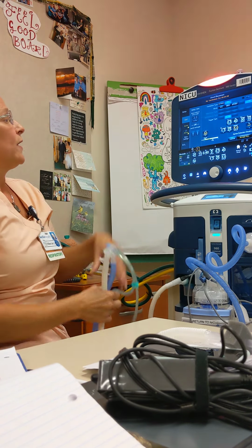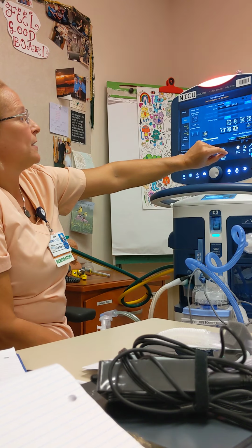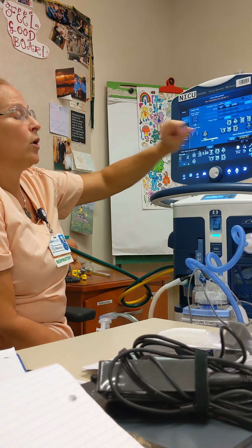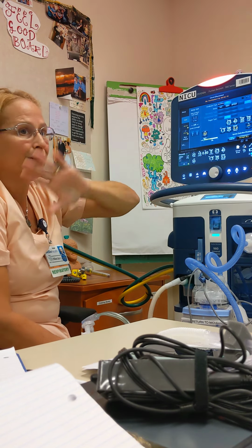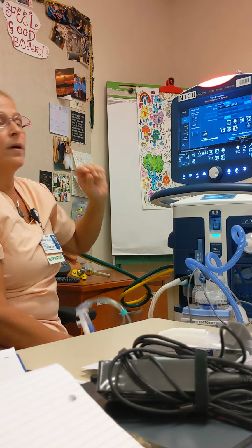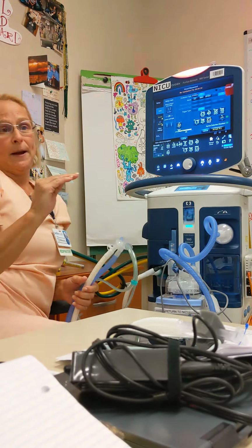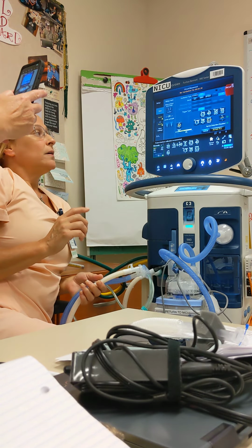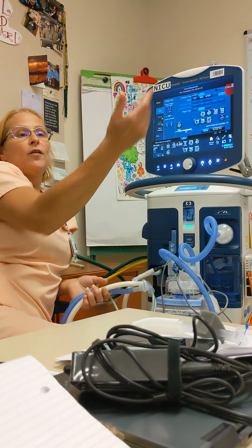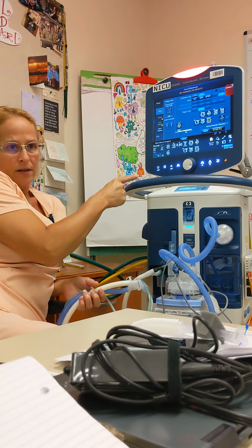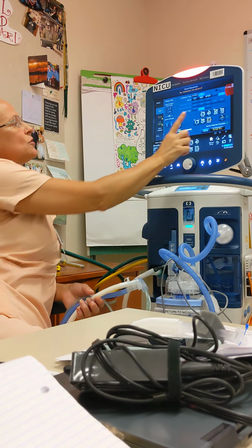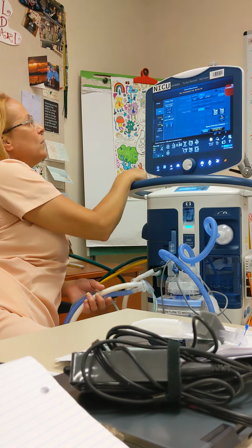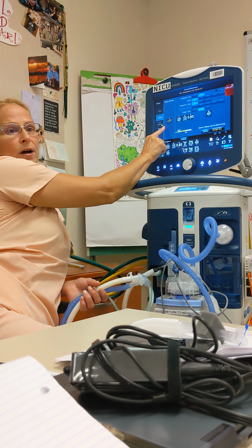Two flashing lights tell you that TA is your apnea time and your apnea detection is disabled. We want it disabled. If they are in CPAP, that means they are fully spontaneously breathing on their own. They're not an apnea-prone baby, which a lot of these preemies are. This is not NIPPV yet. This is just CPAP. All of these babies are already on a cardiac monitor. We do not need this to tell us they're going apneic and the cardiac monitor to tell us they're going apneic. Too many alarms. So we want that off. If you would go into apnea, that's going to tell you it's off as well.